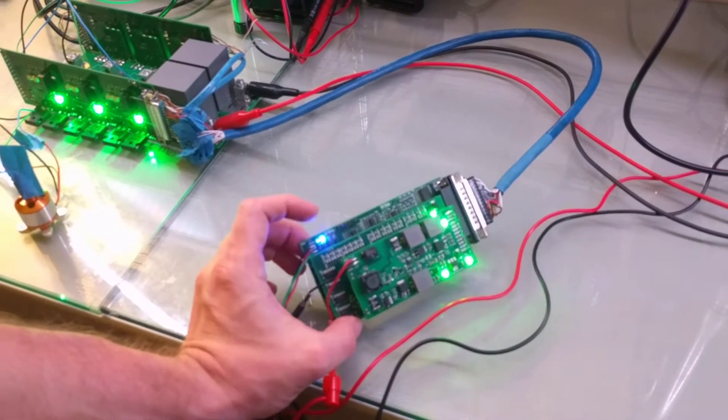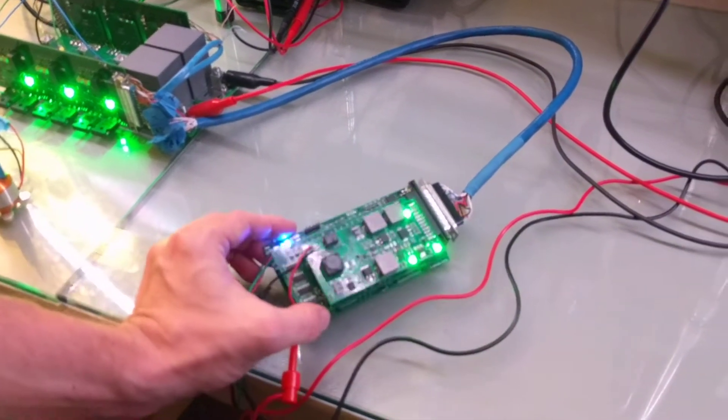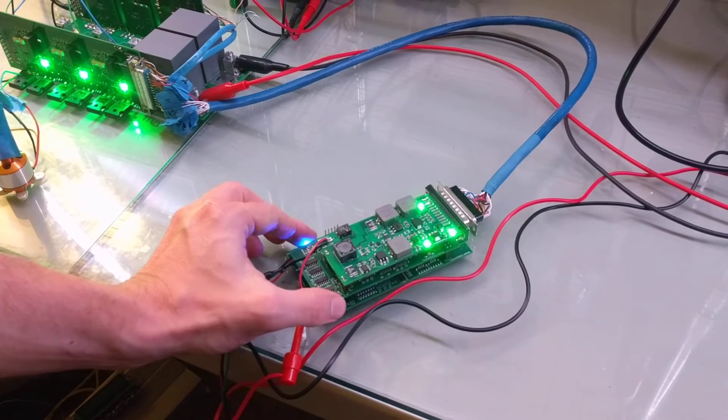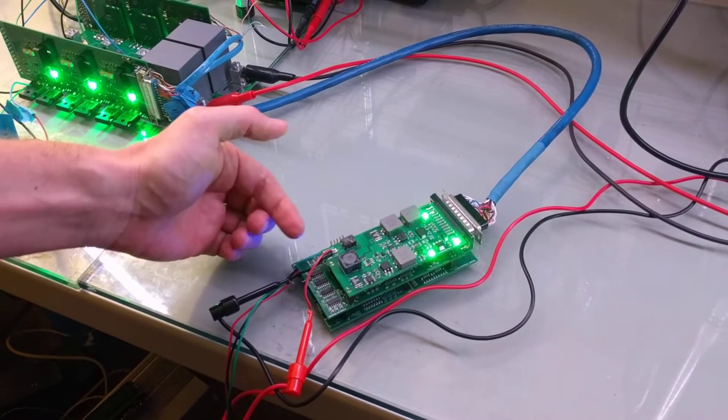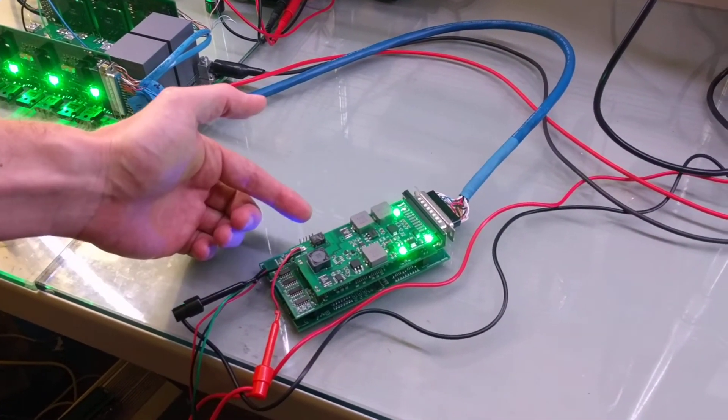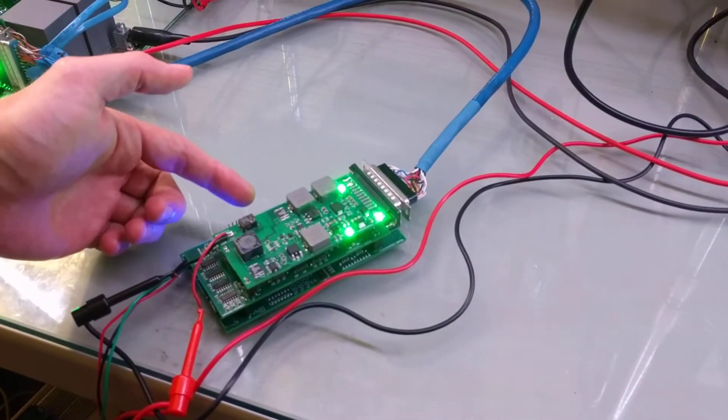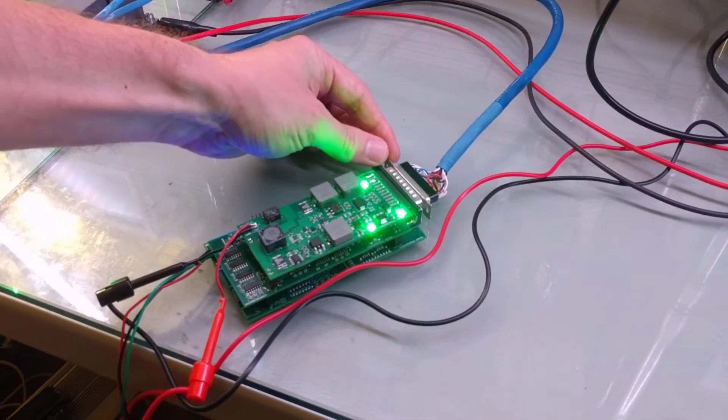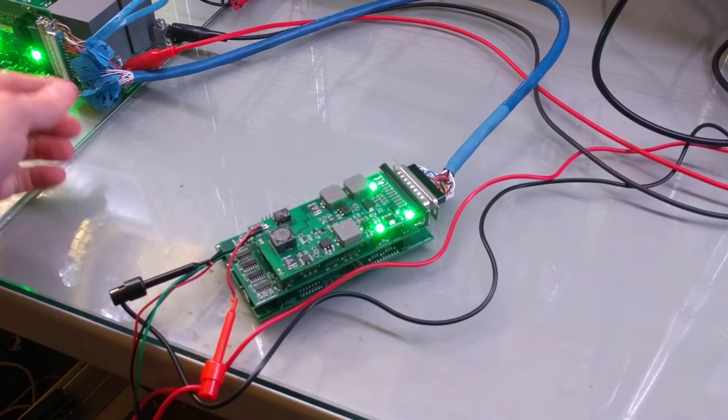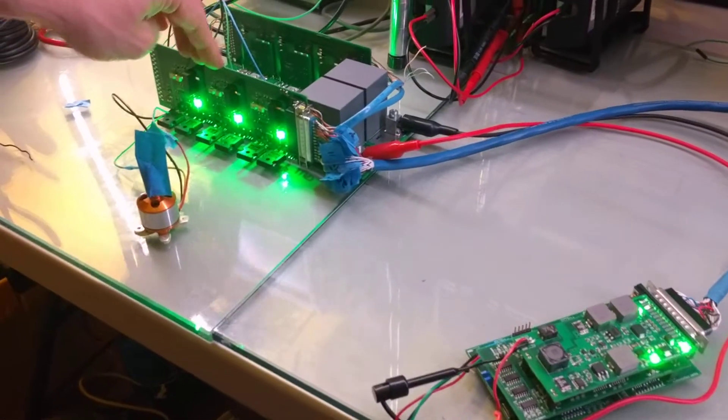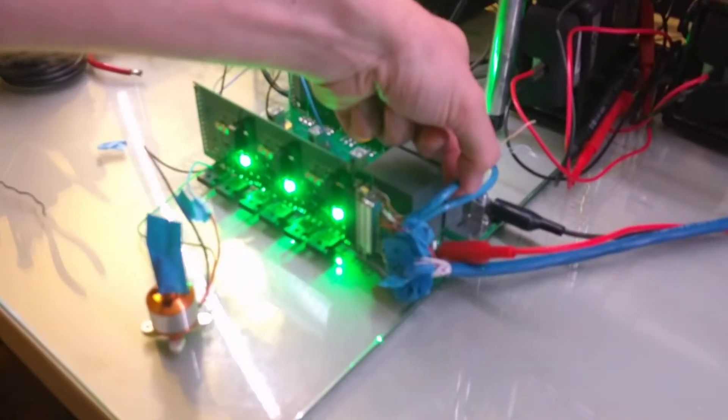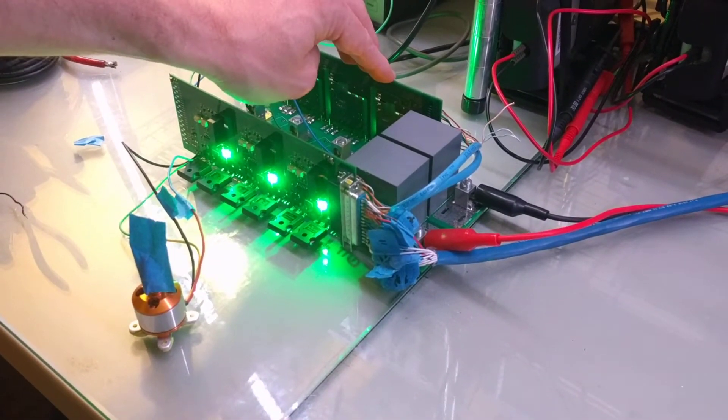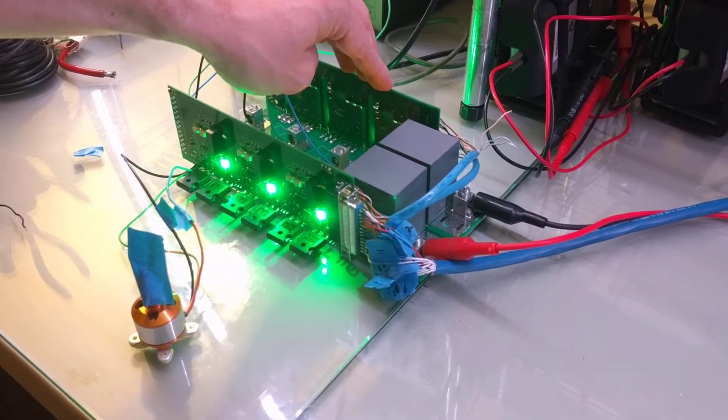Then the bottom board is the VESC main board which contains all the signal processing which goes into the processor and then also into the fault logic board. Everything comes out through a DB25 and then connects in over here to the gate driver board. Two jumper wires coming over to the other gate driver board on the opposite side.